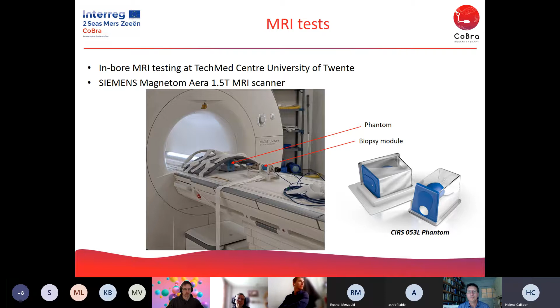So we went to the University of Twente for that and tested in a 1.5 Tesla MRI scanner. Unfortunately, we didn't have access to a 3 Tesla MRI scanner, so that was a slight limitation of this experiment. So we had a phantom and a biopsy module, and we put it inside the scanner, and we did some testing. So here are some images that show some of the results, and as you can see, in this image over here, there are only very limited artifacts from the needle itself.